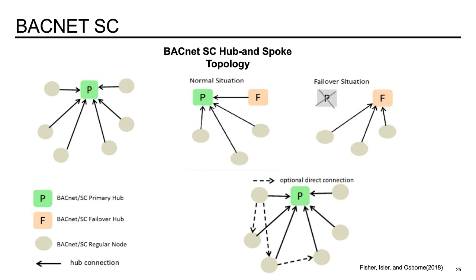BACnet SC provides a detailed failover mechanism to keep the system up or online. If the primary hub fails or is taken offline for maintenance purposes, all BACnet SC nodes are mandated to support reconnecting to the BACnet SC failover hub. So if the primary knows it's going down, it can tell all the devices to immediately connect to the failover. The failover monitors the primary and will send everyone back to the primary immediately when it becomes available. This is designed to minimize downtime in critical installations. It's probably not going to be needed for typical installations, but it is something that is spelled out in the BACnet SC addendum.